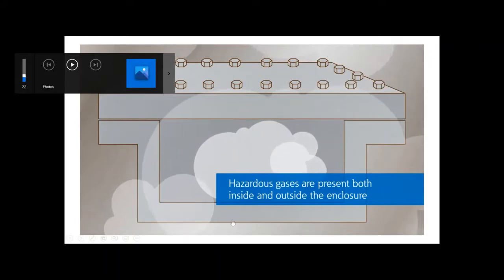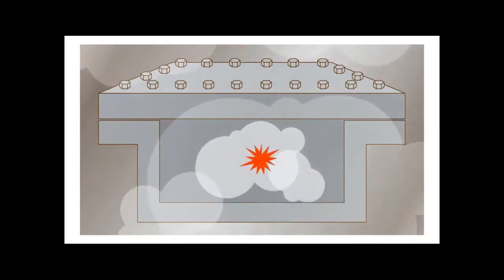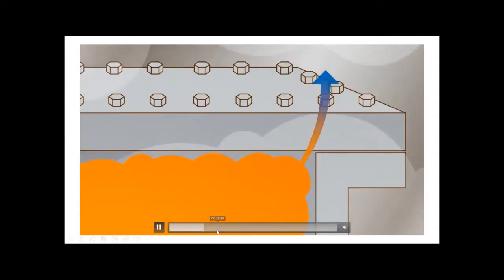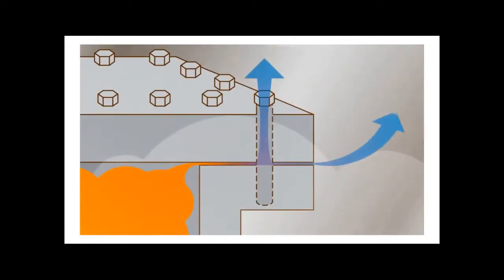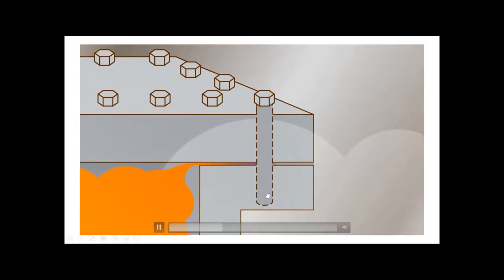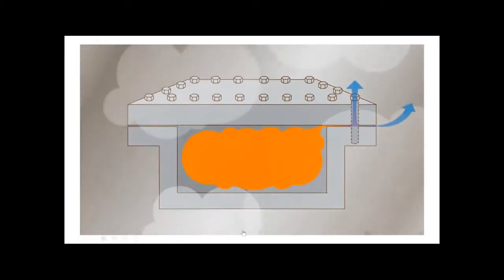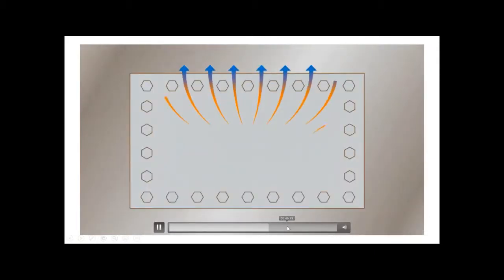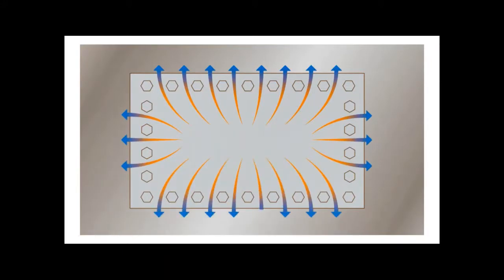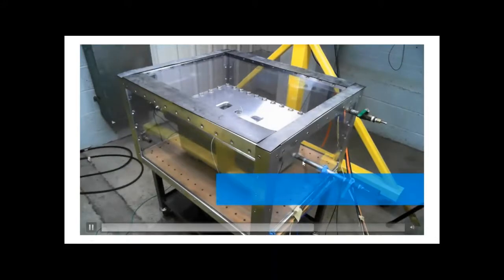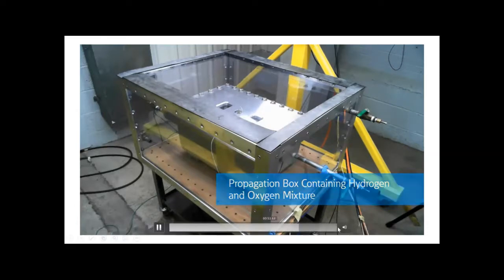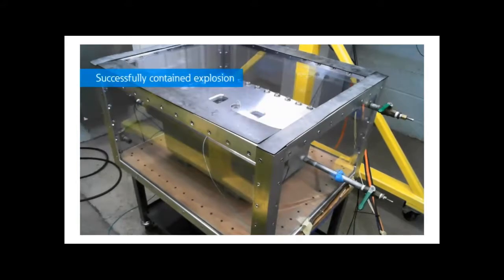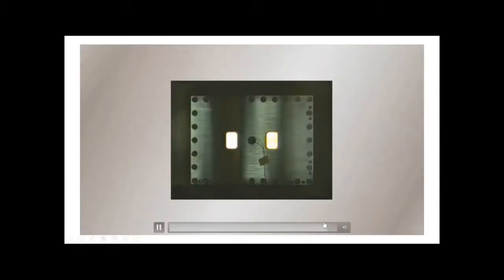Gas is not kept out of the enclosure, even in R.Stahl's ExPressure. The explosion happens inside, and it's released from the flame path, even through the threads of the bolts. Yes, correct. If everything's properly installed, it is safe. So if all the bolts are tightened according to the IOMs, and if every EXD point is considered and observed. Yes. So with a traditional box, the explosion happens inside, and the flames, the heat, and the arcs and sparks do not travel to the outside. So that's a typical EXD box.